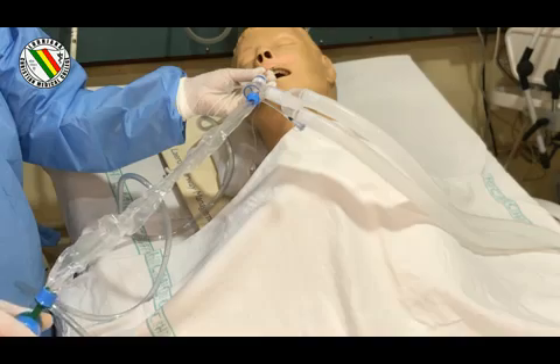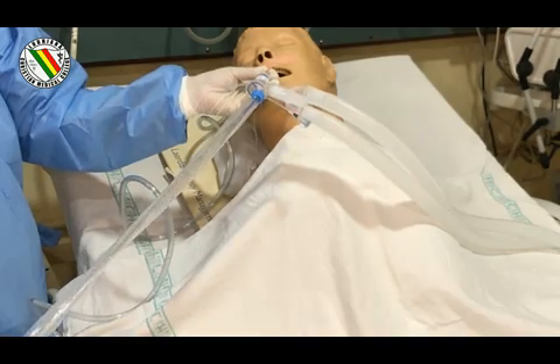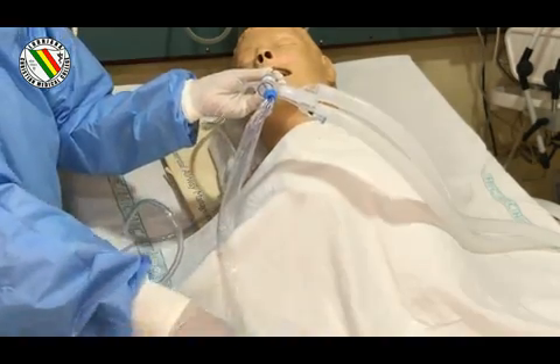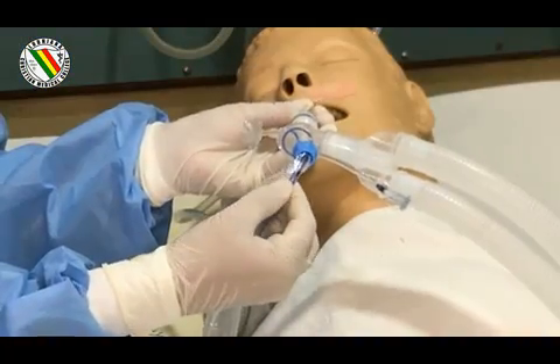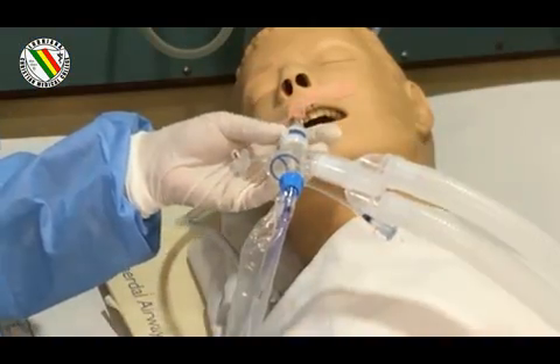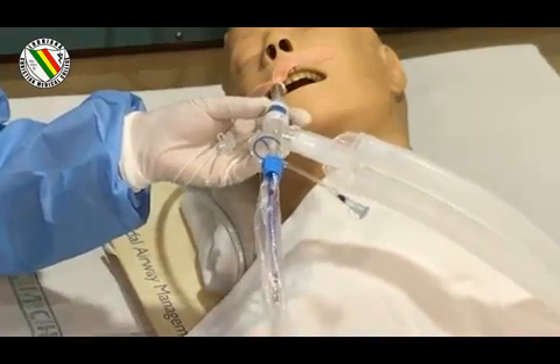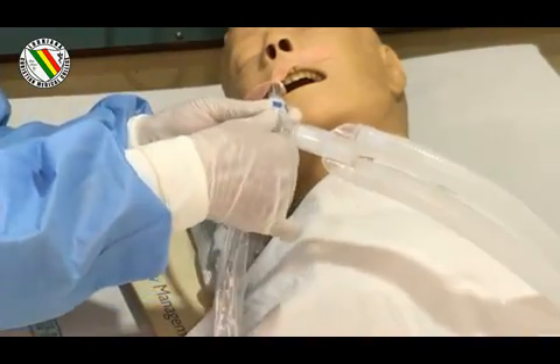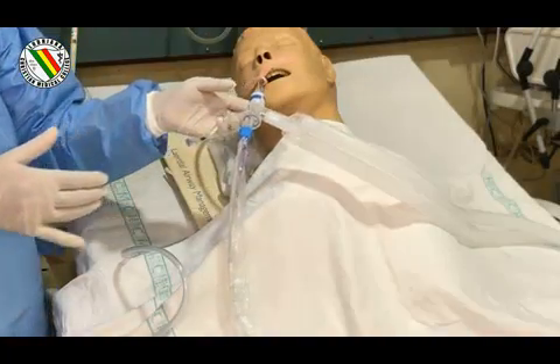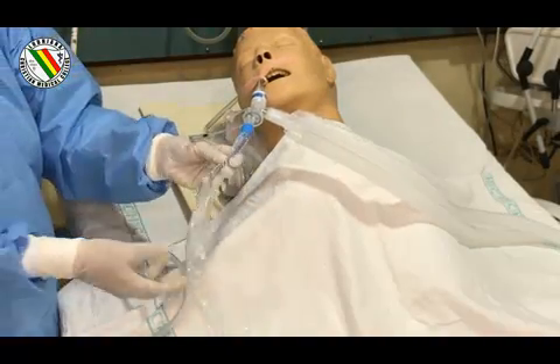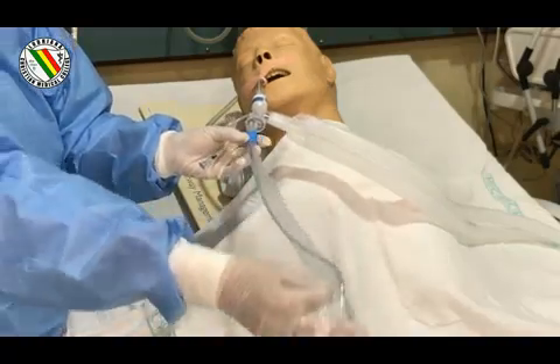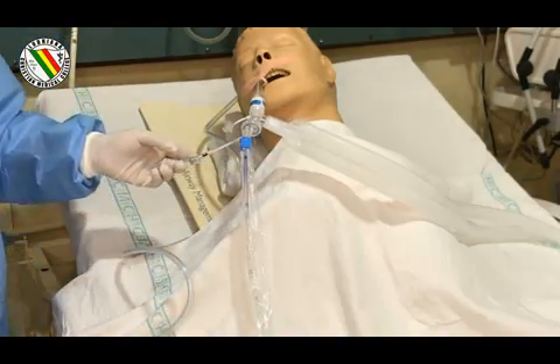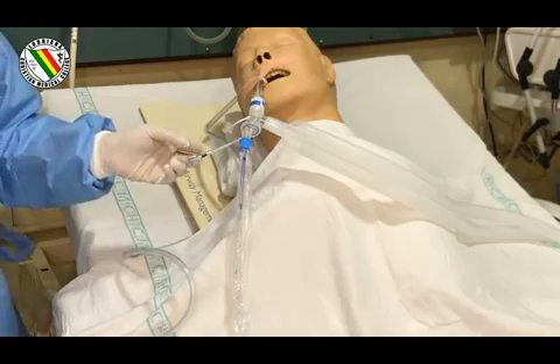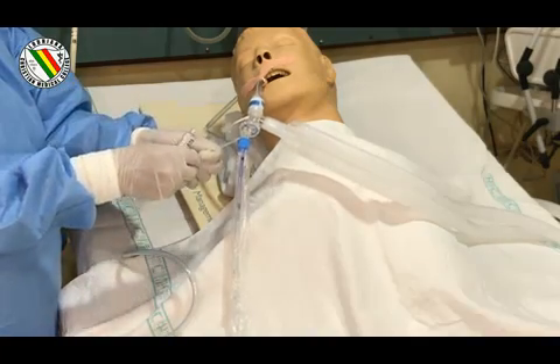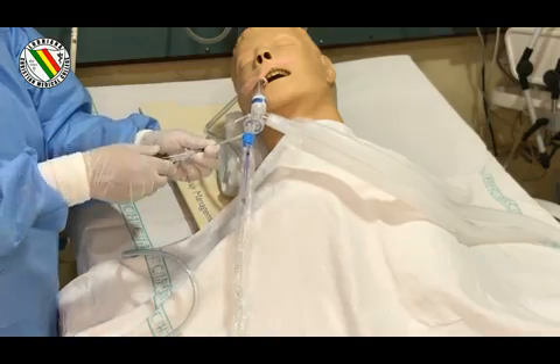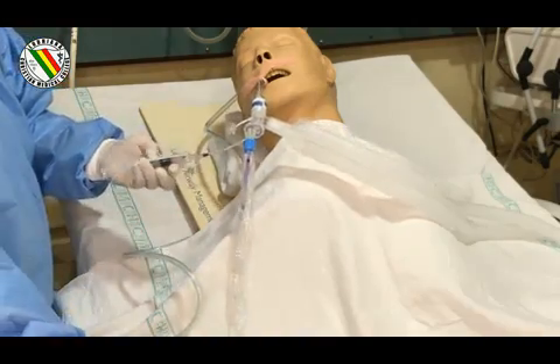Stop withdrawal when the black marker ring appears inside the sleeve, and release the thumb valve and immediately rotate the knob towards the right side. Do not pull too far or you will stretch the sleeve. The irrigation port should be used to clean and rinse the catheter when the suction procedure is completed.